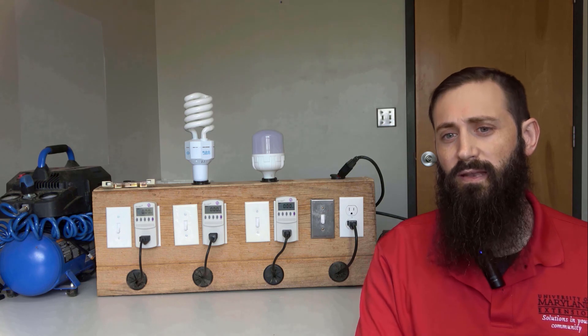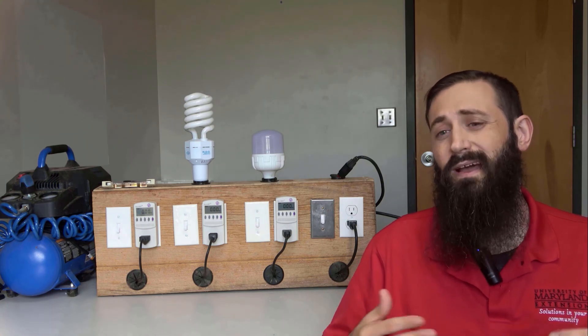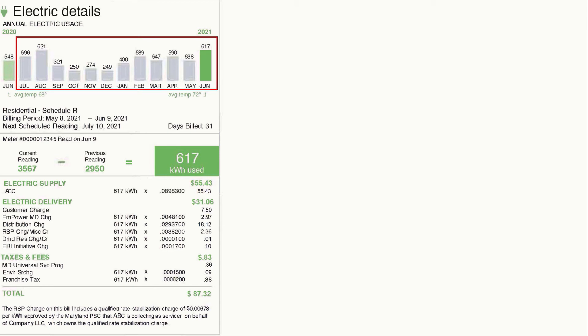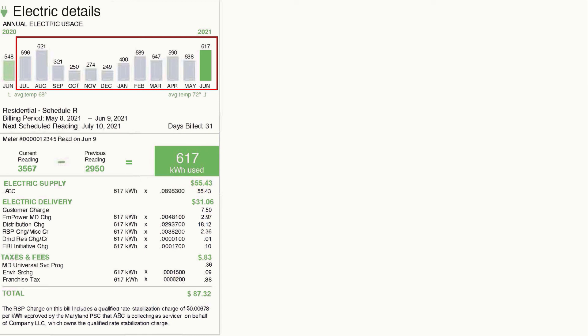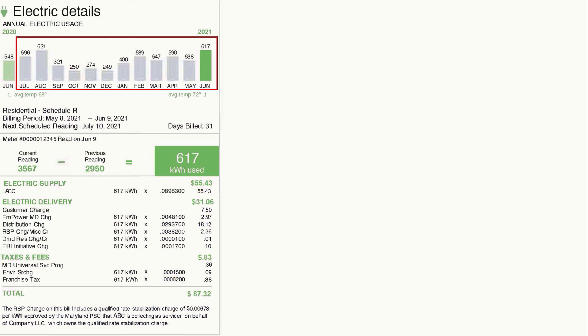Now that we've looked at how to assess individual electric loads, we'll use a standard electric utility bill to consider the energy load of an entire building or operation. A utility statement will vary from one utility to the next, but we'll focus on the electric usage history shown on this particular bill. The units for energy are given in kilowatt hours (KWH), and energy consumption is summarized for each month over the past year. The summer months — June, July, and August — have higher energy consumption, perhaps due to air conditioning, while smaller spikes in January and February may come from fans or blowers within heating systems.